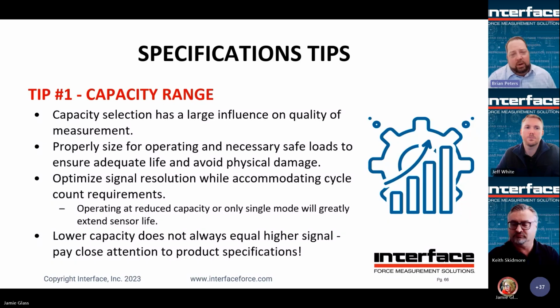The other thing to pay attention to is, just because you may find another load cell somewhere else, pay close attention to what the signal output is. It is commonplace for some people. We don't do it very often, only on a couple of products where we'll offer a half calibrated load cell as a specific capacity. Most of the time we try to maintain the same output across all stated capacities. So again, you may be thinking you're finding a load cell that's rated for half the capacity, meaning you're going to have better signal or better measurement, but in reality, you're just getting half the output.